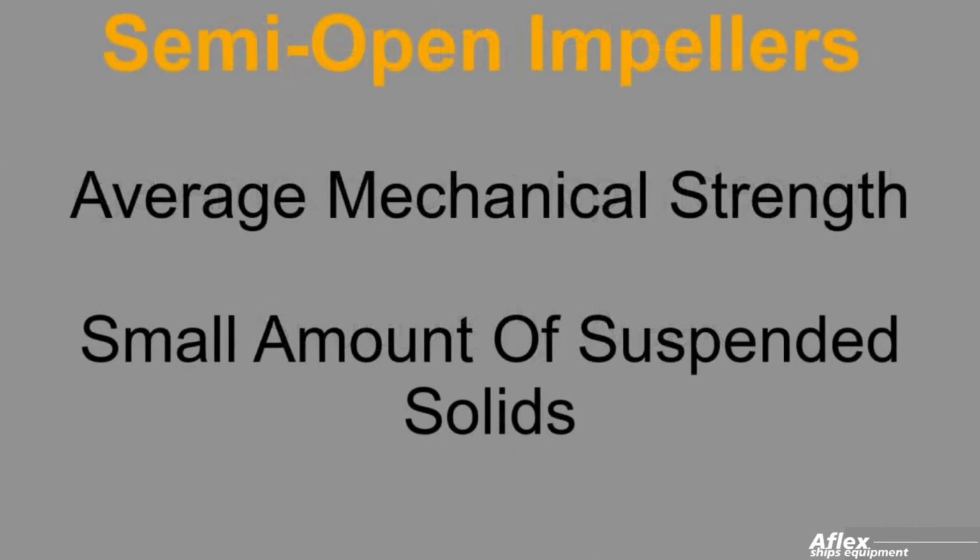Semi-open or semi-closed impellers have a greater mechanical strength than open impellers due to the shroud where the vanes are mounted. This type of impeller is ideally suited to handle fluids with small amounts of suspended solids.